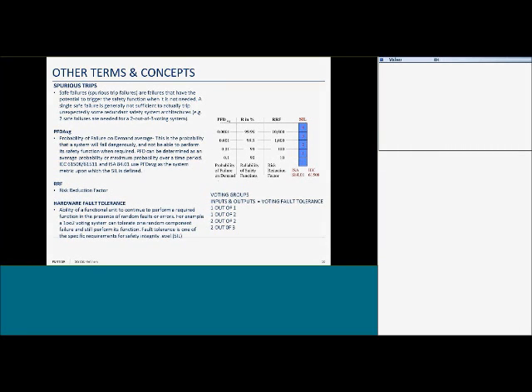What a SIS engineer does is they sit down and take the certificate for each of the components: the sensors, the logic solvers, the final elements, which includes the valve, the actuator, the controls. They take the PFD average from each one of these certificates and put them into a deep dive analysis software, typically software like SIL Solver or Exida.